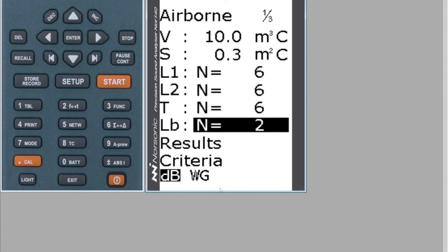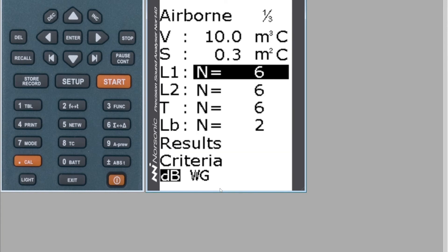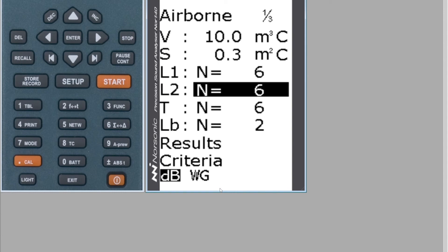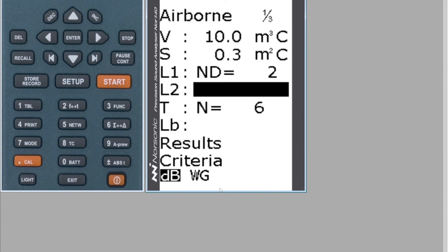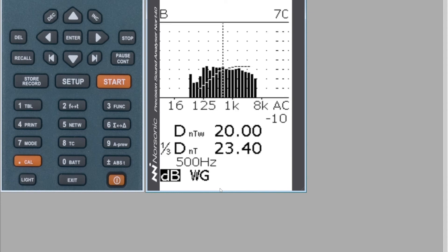To linearly average the other speaker position, go up to L1, L2, T, or Lb — any of these fields, it doesn't matter which one — and press the Recall key. When you see the Recall key, you now need to call in your speaker position B file, which was file number 22 — the one with just your L1s and L2 measurements. Press Enter on number 22 and the meter will linearly average the two speaker positions. It should say ND equals 2 for your two positions, and N equals 6 for the reverberation. Go down to Results and you'll have your DnT,w — the value is slightly different, it's now 20.